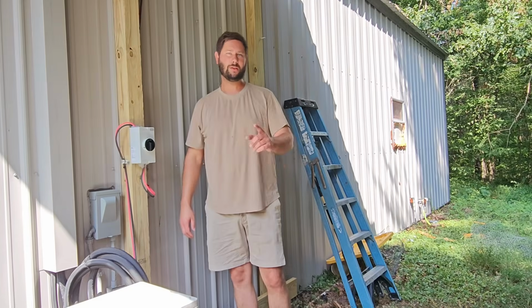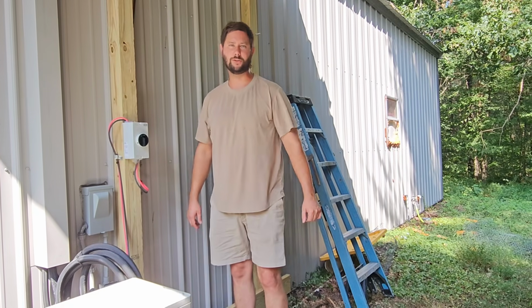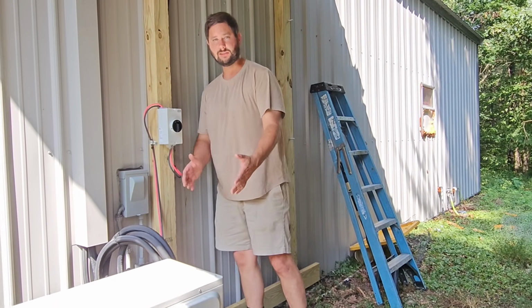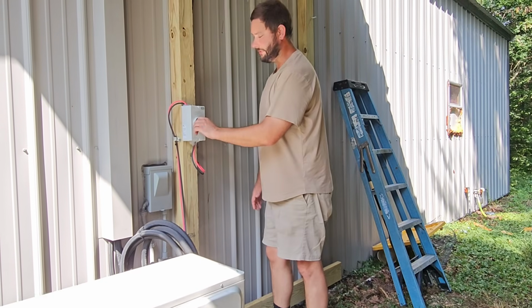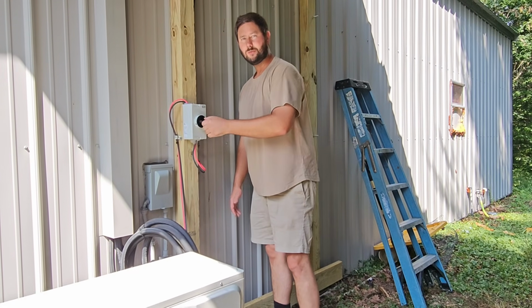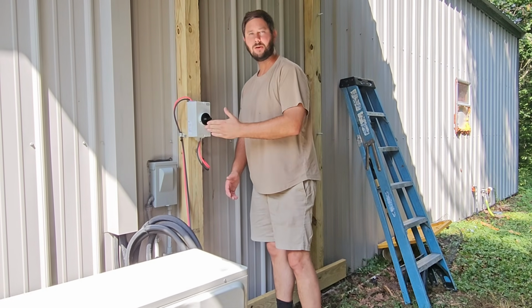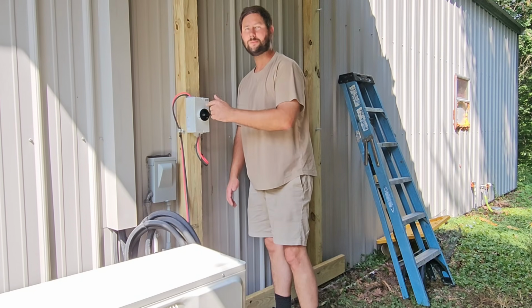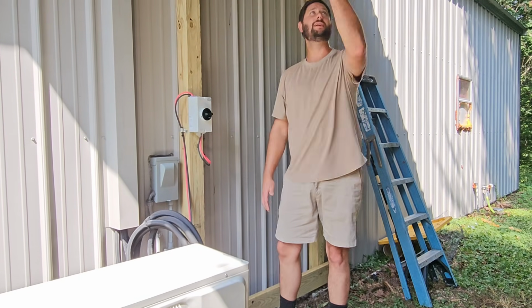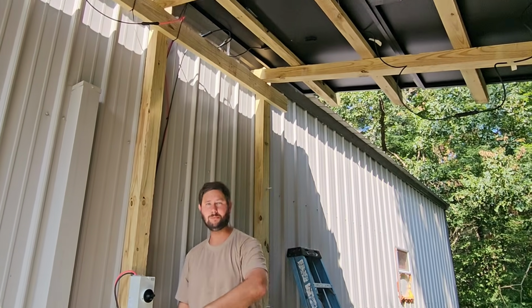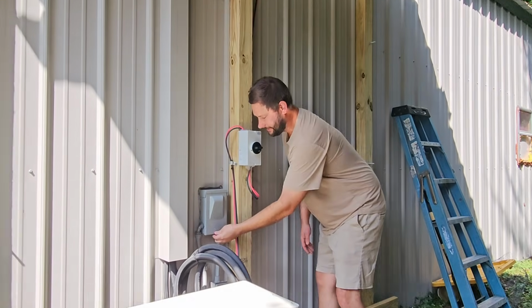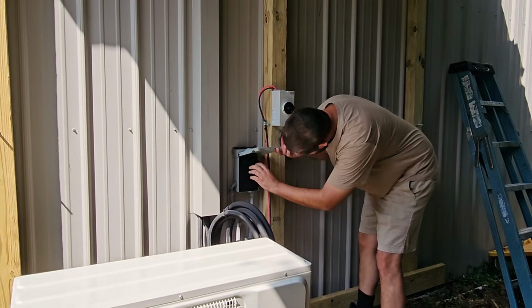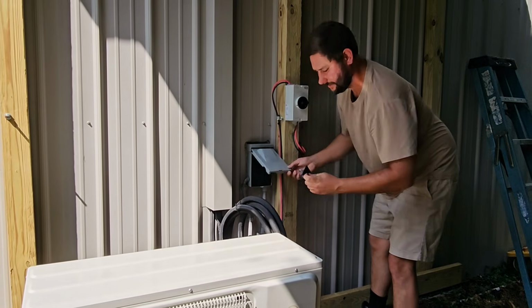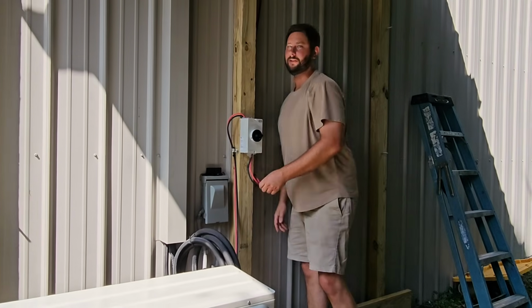Let's get started. The first step for recovering the refrigerant is you got to make sure that the mini split doesn't have any power. This is a solar powered mini split, so we got to cut the DC power, which we just cut by turning off the PV isolator, isolating the solar from the mini split. And now we're going to take the AC disconnect and pull that disconnect, and that will completely shut off the unit.